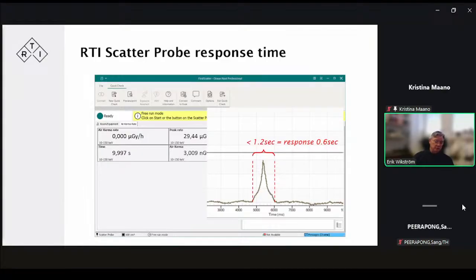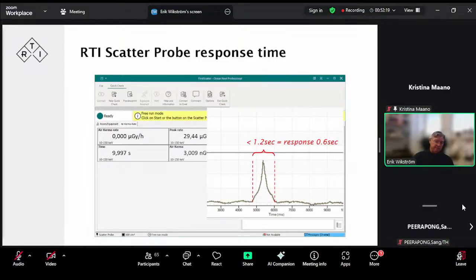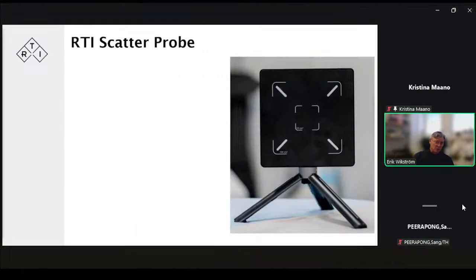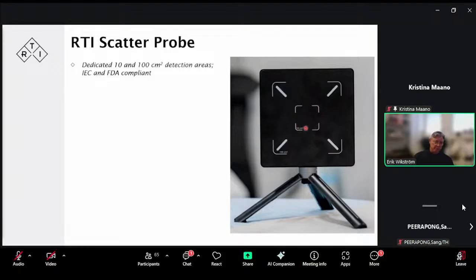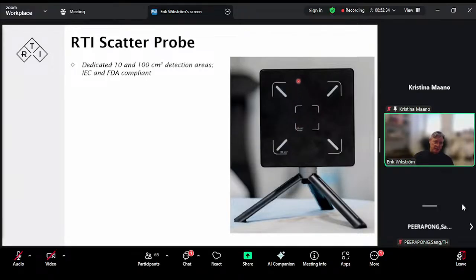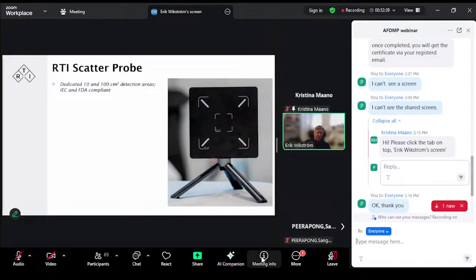And also for radiation with very, very low dose rates that we've got here. This is what it looks like in a close-up. We've got a 10 square centimeter area for some of the steady state applications, and we have a 100 square centimeter area right here for most of the leakage radiation, and also for scatter radiation. So it's compliant with both IEC and FDA.